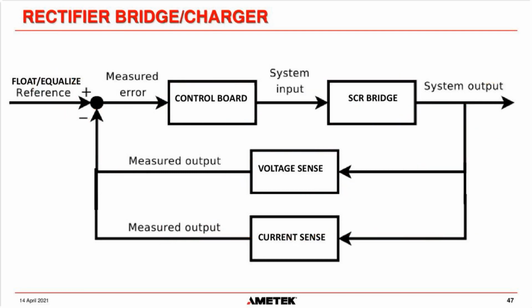So this feedback circuit is constantly sensing the output of the system all the time, and it's constantly adjusting as necessary to whatever the float voltage, or the equalized voltage, has been set to.